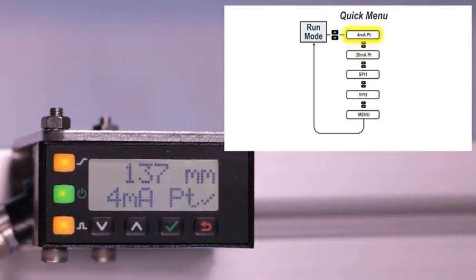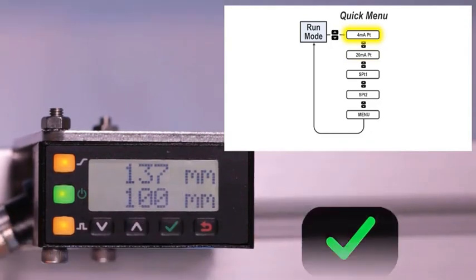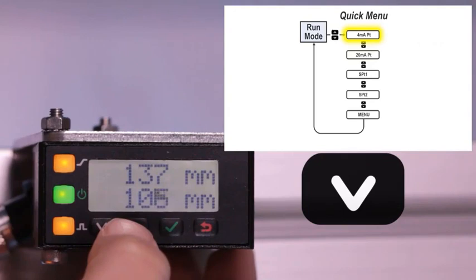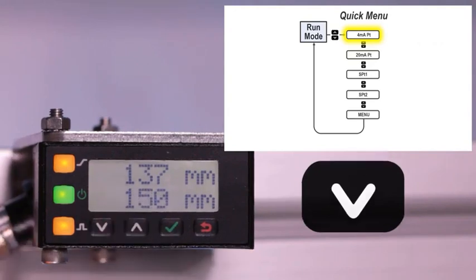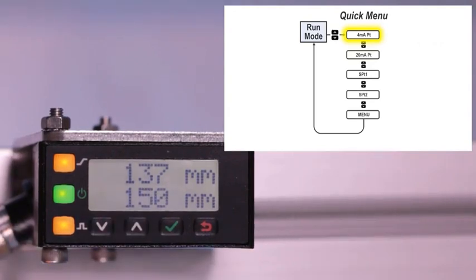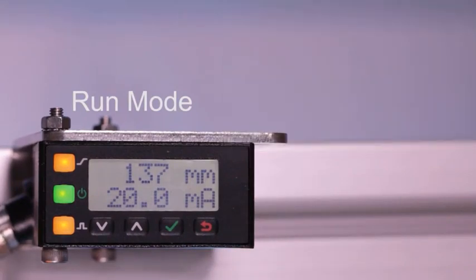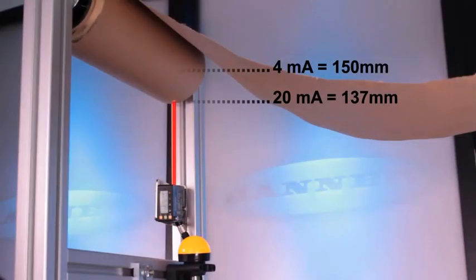Click enter and the 4 milliamp value will now start flashing, indicating that the up and down buttons can be used to manually adjust the value without having to present a target. Because the core diameter is known to be at 150 millimeters, the 4 milliamp point can be set at 150 millimeters without having to unwind the roll to present a target.